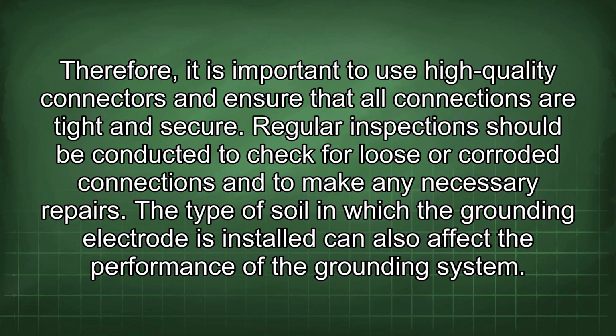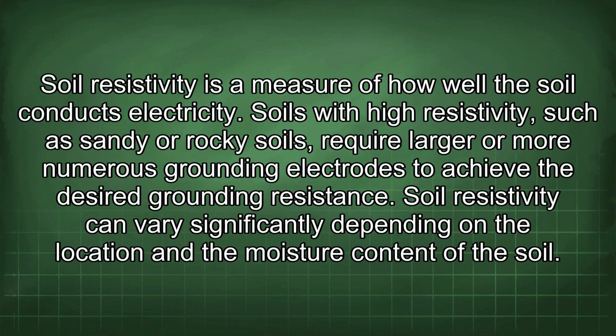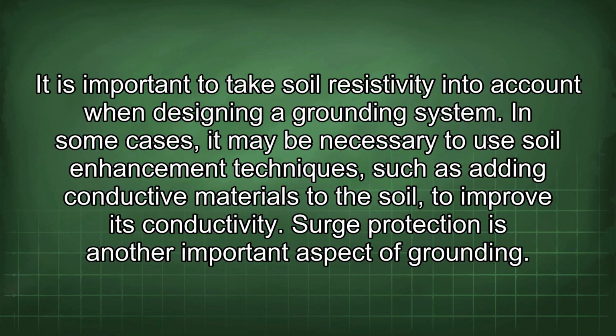The type of soil in which the grounding electrode is installed can also affect the performance of the grounding system. Soil resistivity is a measure of how well the soil conducts electricity. Soils with high resistivity, such as sandy or rocky soils, require larger or more numerous grounding electrodes to achieve the desired grounding resistance. Soil resistivity can vary significantly depending on the location and the moisture content of the soil. It is important to take soil resistivity into account when designing a grounding system.